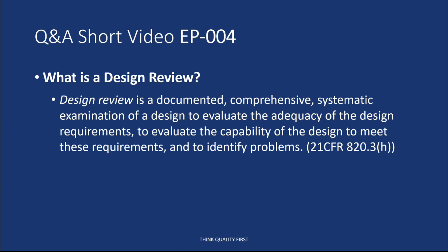21 CFR 820.3(h) gives the definition of a design review. Let's take one step back and look at the term review. Review is a commonly used word to describe an assortment of design assessment activities. Most, but not all, of these activities meet the definition of a formal design review.